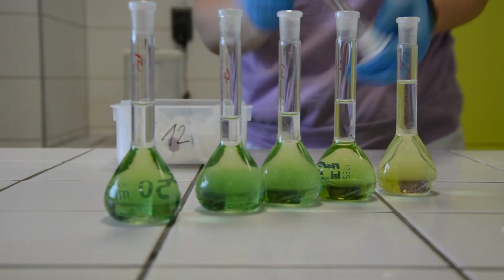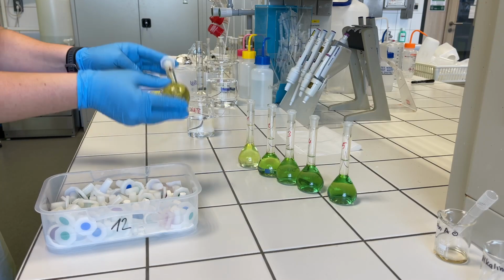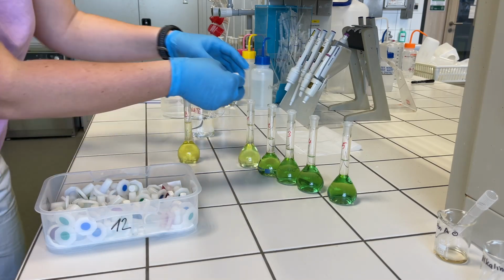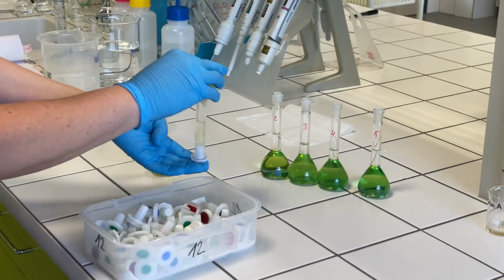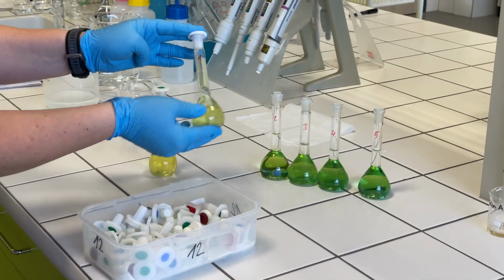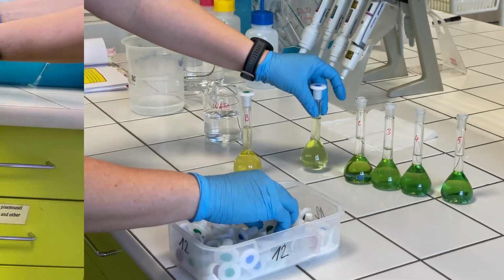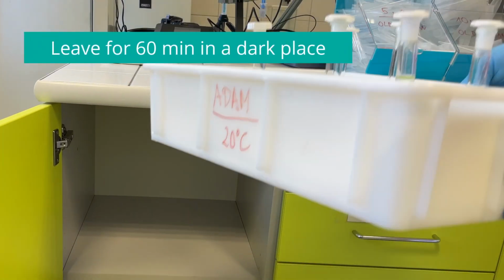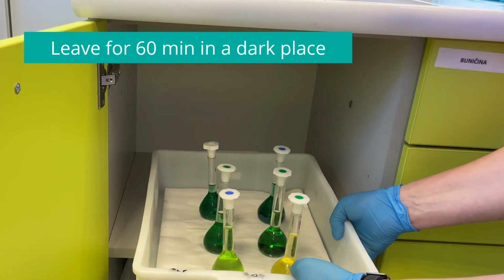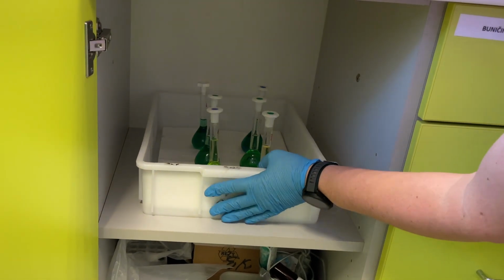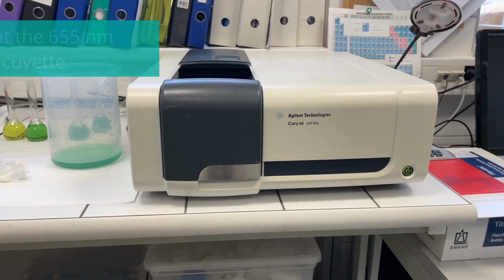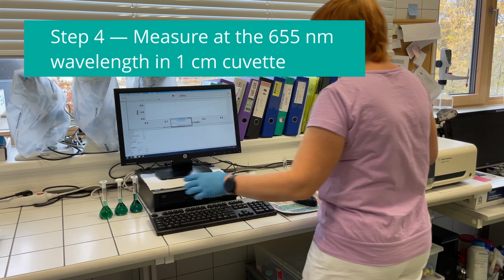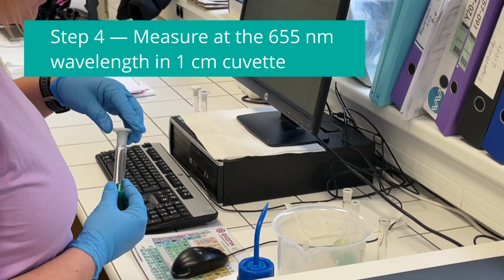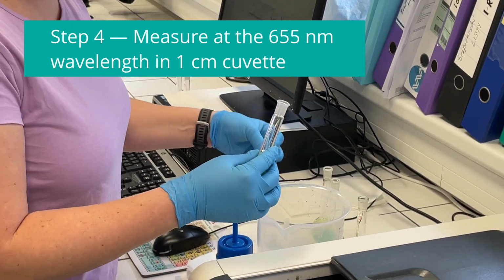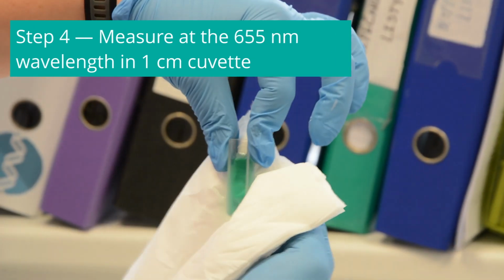And stir thoroughly. You should see a smooth, light to dark colour gradient with increasing concentration. If not, remake from the stock. Leave in a dark place for at least 60 minutes. Measure each standard and the blank at the 655 nanometer wavelength in a 1 centimeter cuvette.